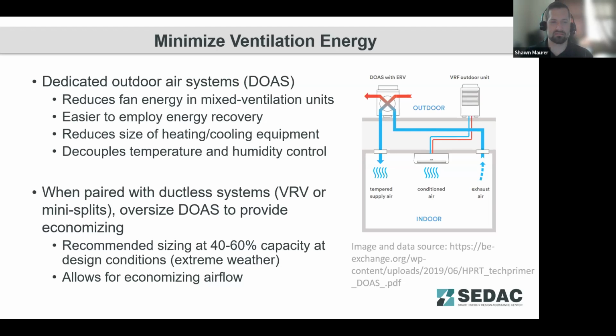and you're decoupling temperature and humidity control for ventilation air. So you do humidity control through that dedicated outdoor air system. You temper that air to a mild neutral condition, somewhere around like 65 degrees and 55% relative humidity might be common. Send that to the space, and then you've got a heat pump in the space or a terminal unit there that's doing most of the recirculating for that dedicated space, and then conditioning that air in that space with cooling coils and heating coils.